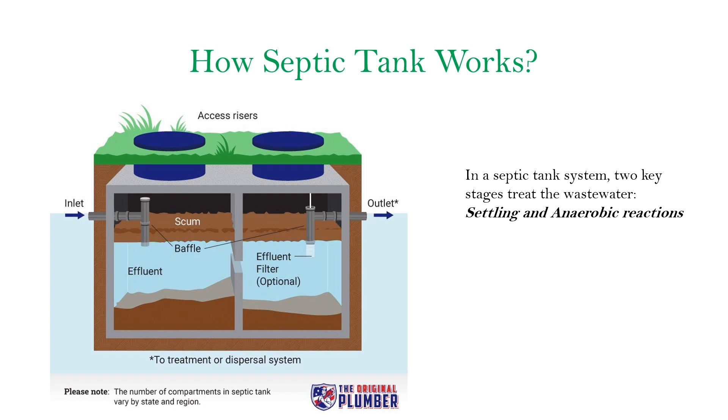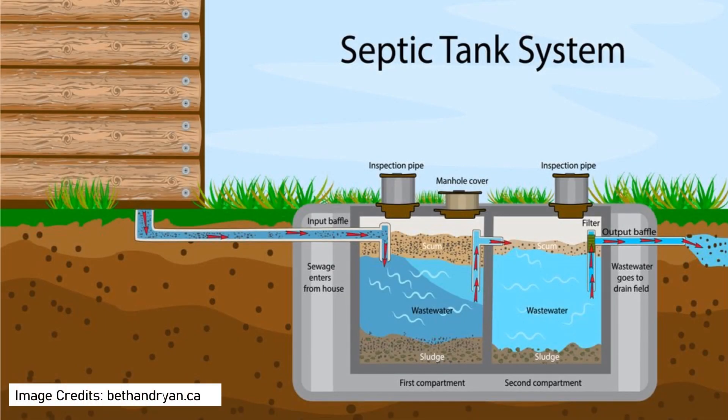The wastewater entering the tank separates into three parts: solids, effluents, and scum. Solids sink to the bottom and turn into sludge. The solids are decomposed by microorganisms in the absence of oxygen, thus forming the main anaerobic reaction in the system. At the same time, the scum, like oil and grease, floats on top.